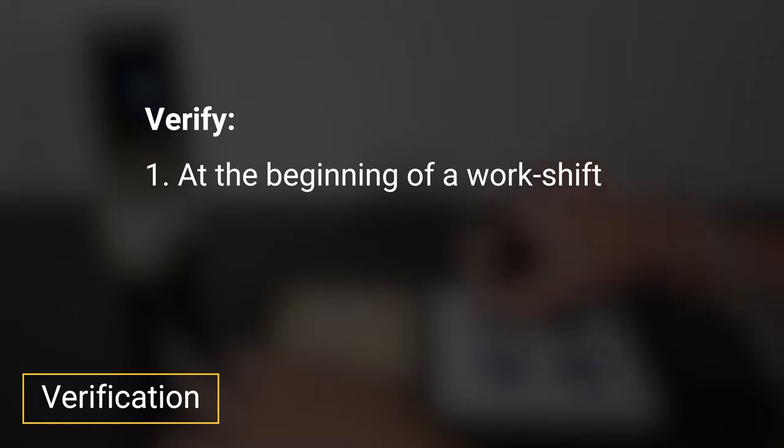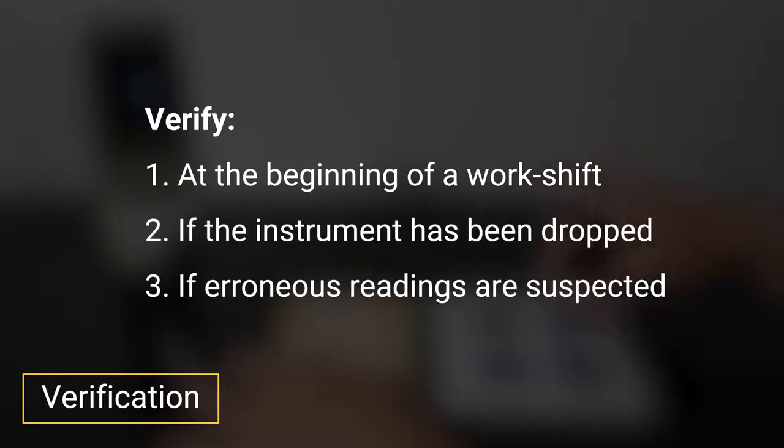Step 2: Verification. Verification is typically performed at the beginning of a work shift, if the instrument has been dropped, or if erroneous readings are suspected. It ensures that the PosiTector 6000 is measuring accurately at the time of use.